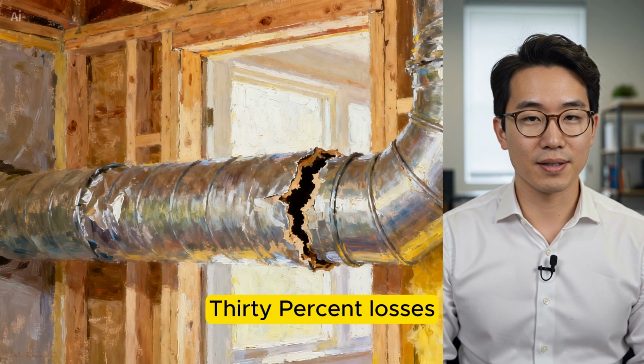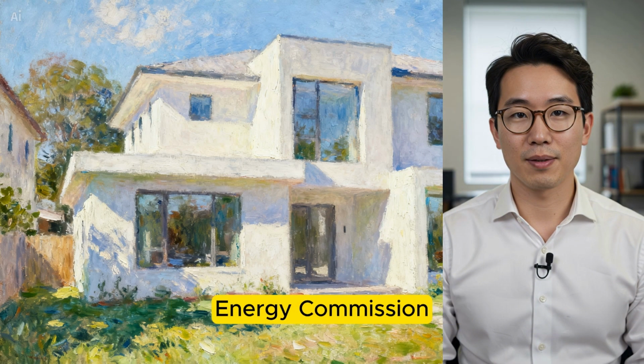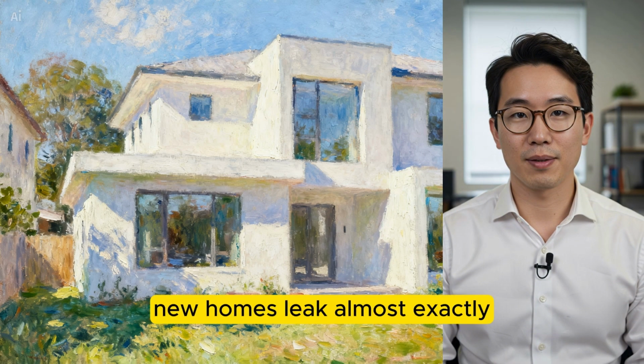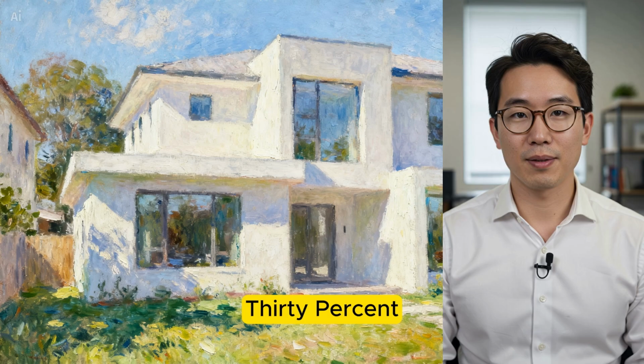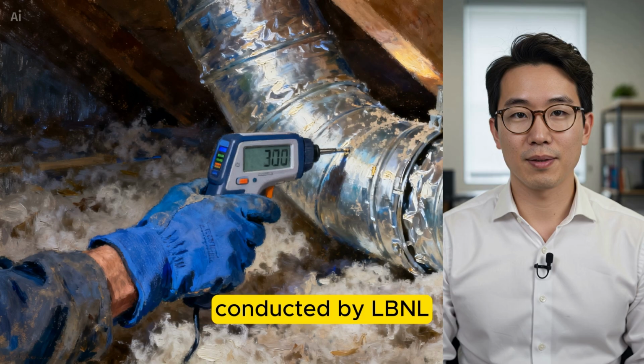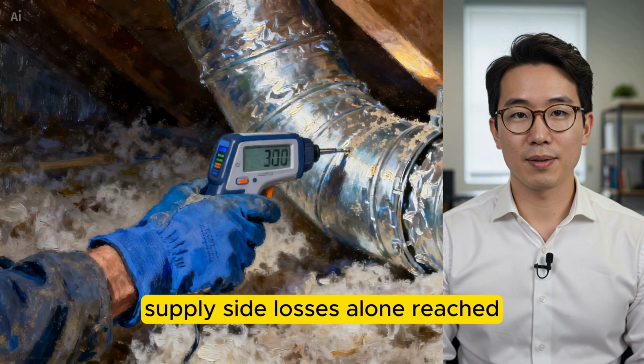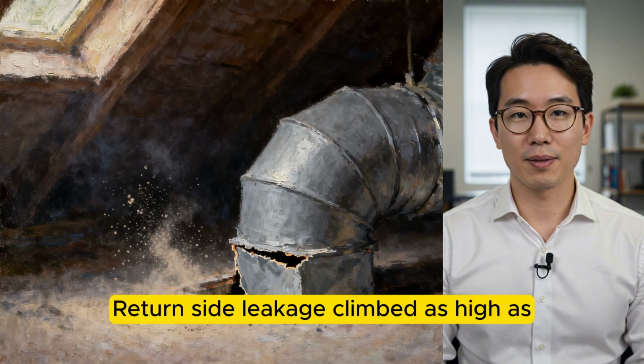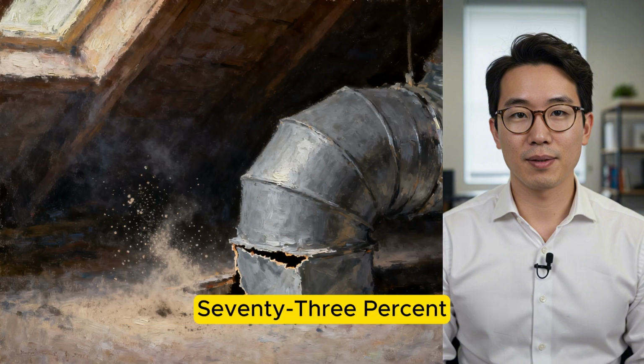Newer houses with sloppy construction, older homes with deteriorated seals, and systems rushed during installation regularly exceed 30% losses. Officials from the California Energy Commission estimated that standard new homes leak almost exactly 30%. In separate field measurements conducted by LBL, supply-side losses alone reached 35%. Return side leakage climbed as high as 73%.